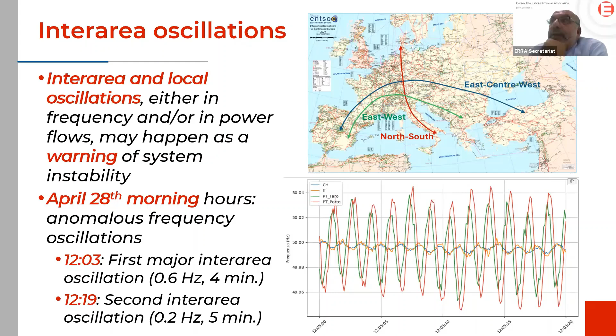Two of these events occurred, one at 12:03 and the second at 12:19 - only a few minutes before the blackout. These inter-area oscillations are not in themselves very dangerous, but there is a protocol to damp and mitigate them, and according to this protocol, the interconnection must be set in a given way named constant DC power.